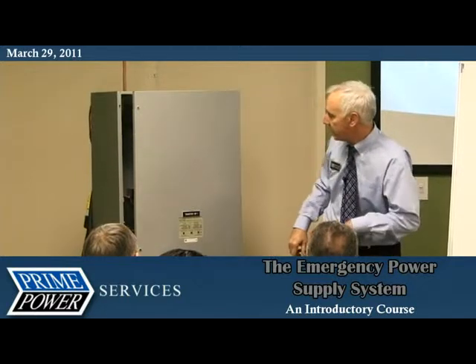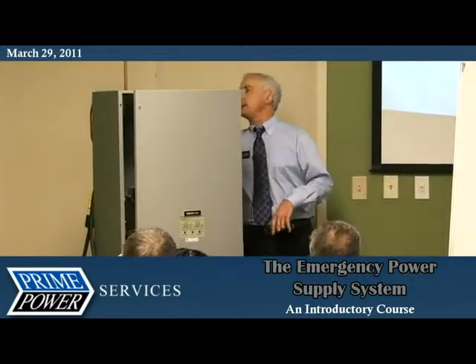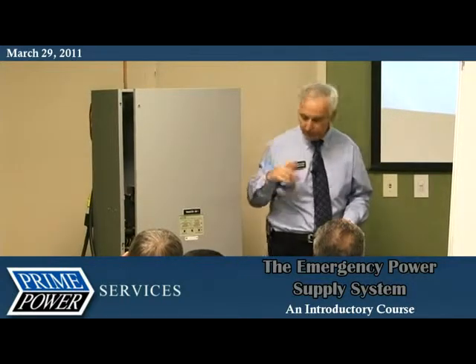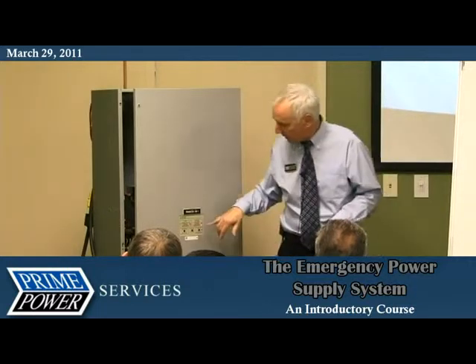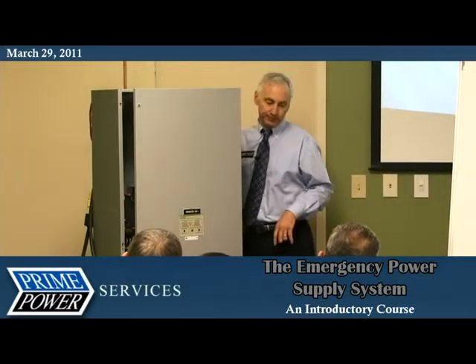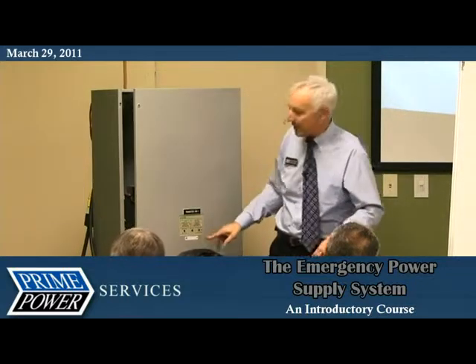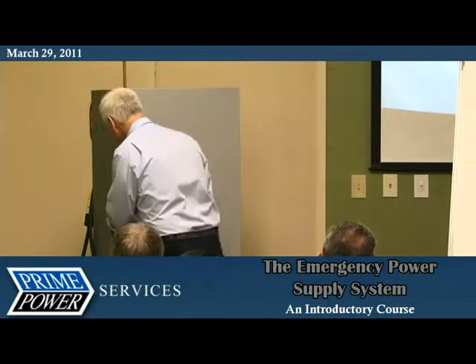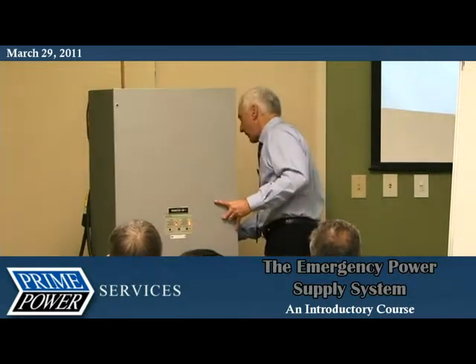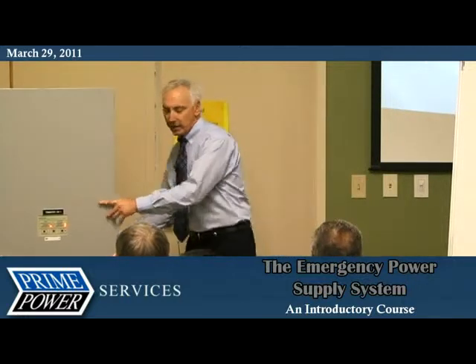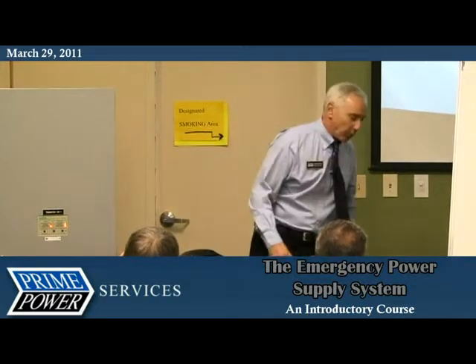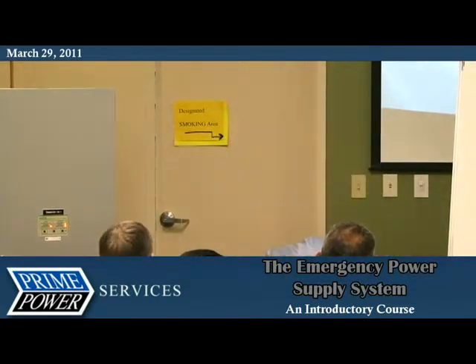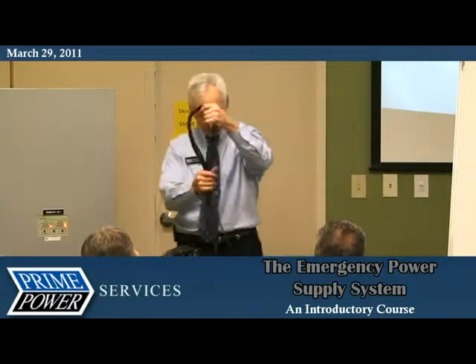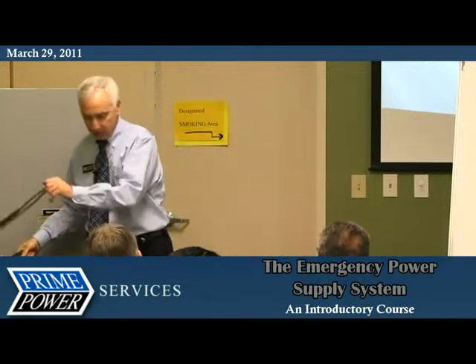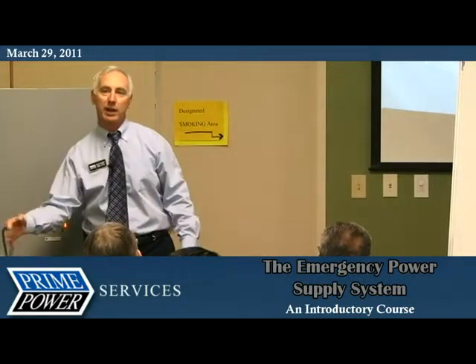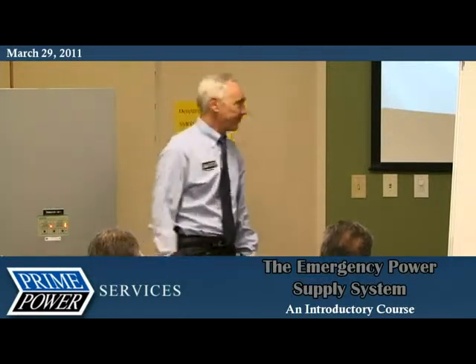So this one is sending a start signal. If I re-enable emergency power, it goes back to emergency. So then if I re-enable normal, then it starts timing, and we'll let this one time—kind of like an egg timer. And if you ever become impatient and want to make this switch transfer back to normal, and you don't have this button on it, the easiest, quickest way to make it transfer is to open the door and look at it. Right as you open the door, it switches.